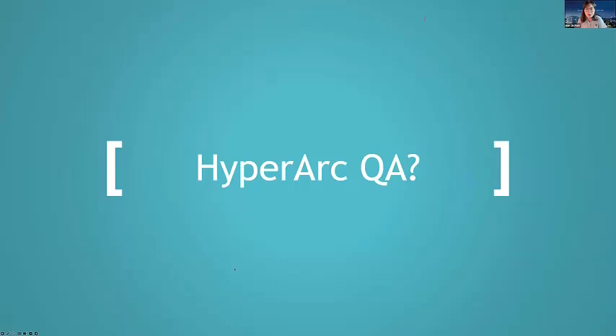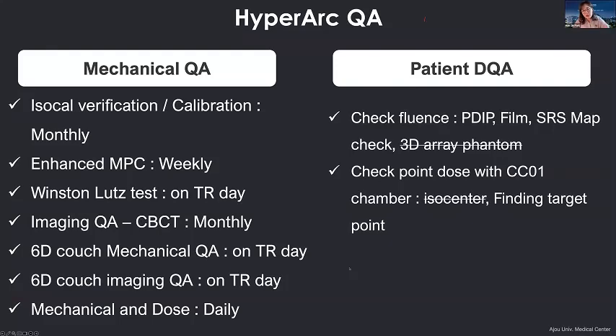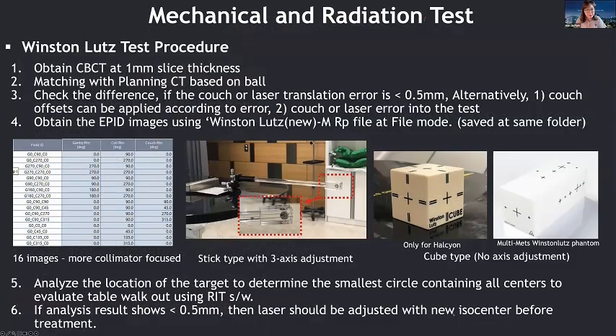Now I'm going to talk about the QA for HyperArc. QA can be divided into 2 parts: mechanical and patient QA. We check some items through the MPC and PDIP provided by the Varian company, but we are also doing additional QA solutions for accurate management. We are checking the Winston-Lutz test on the HyperArc treatment day, using a stick type of phantom that can adjust the 3 axes together. We are checking the isocenter position through a total of 16, and sometimes 12, angles, and it has been managed at 0.3 millimeter on average so far.